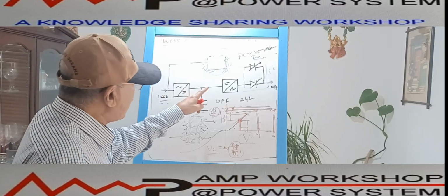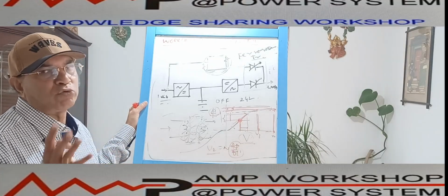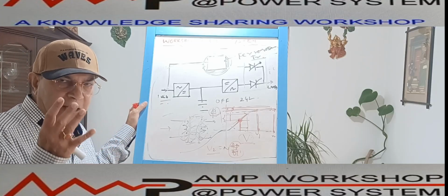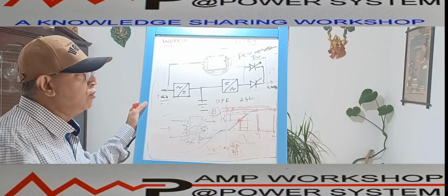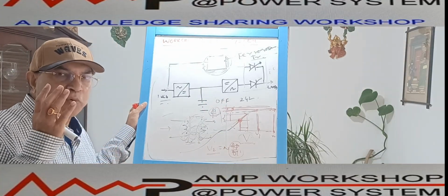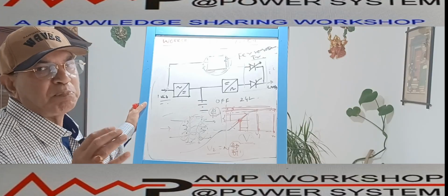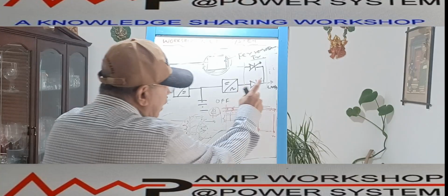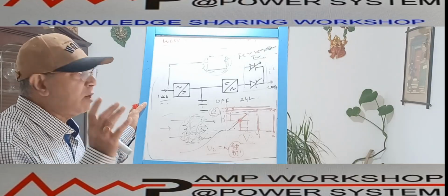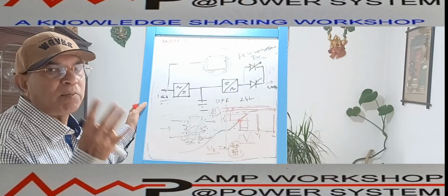So whether we are using a buck boost transformer or a ferroresonance transformer, we can reduce the harmonics to some extent due to the differential property of this. Whatever amount of harmonics the buck boost transformer can reduce, in the case of the ferroresonance transformer that can be reduced more. So the ferroresonance transformer will provide a constant output voltage as well as more or less pure electrical energy to the load. The buck boost transformer also will give a good profile voltage, but the harmonics will not be so good as this, though it will also reduce the harmonics with respect to the normal offline UPS system.